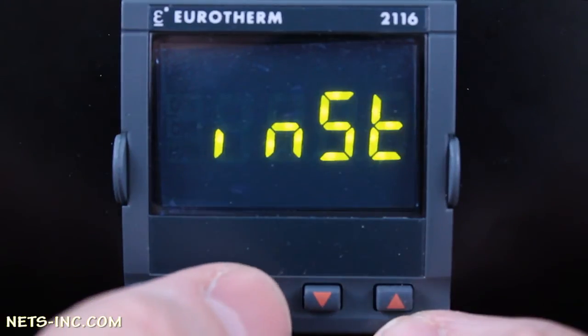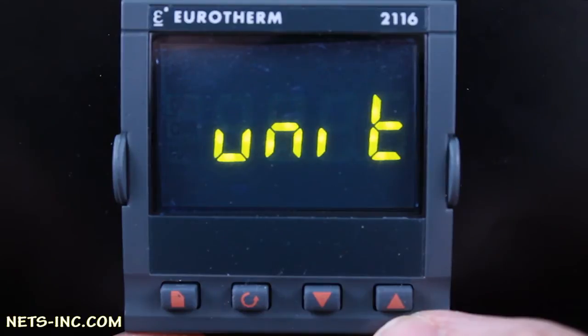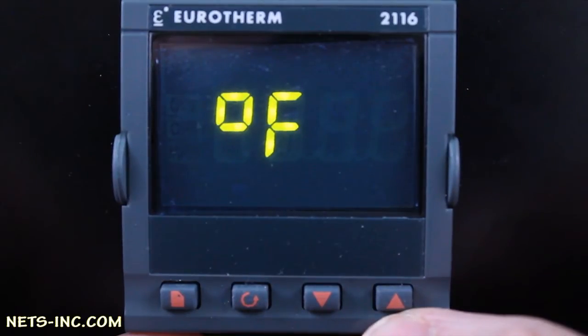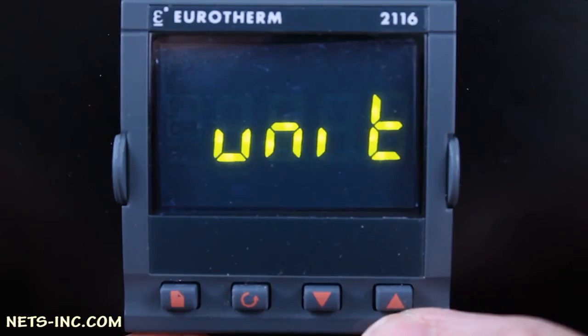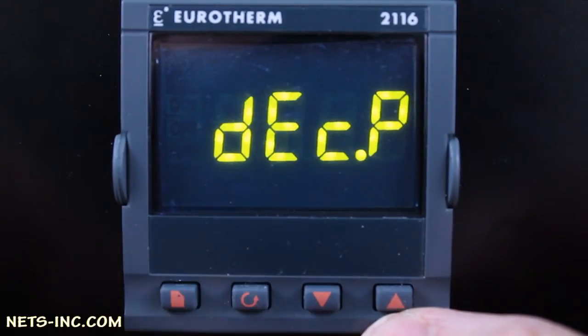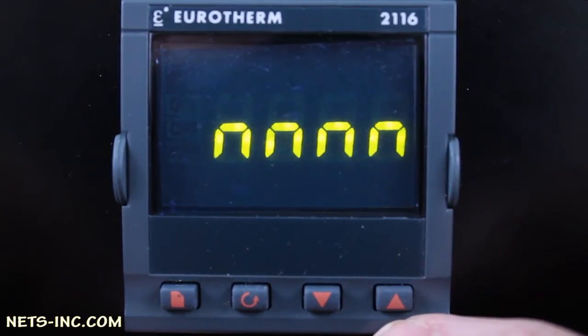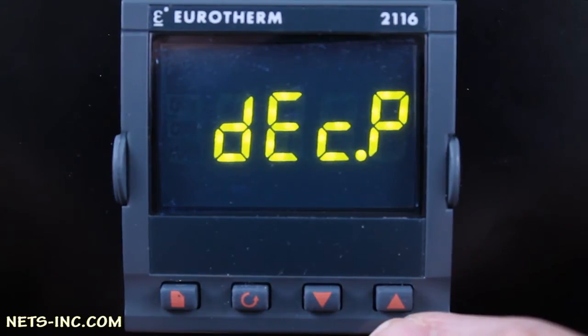With the display reading INST, press the scroll key once to drill down into the INST list and you will notice the display reads UNIT. Press the up arrow and the unit is set up in degrees Fahrenheit. To change it to anything other than degrees Fahrenheit, continue hitting the up arrow and more selections are available. Press the scroll key again and the display will read DEC.P, which is decimal point. Press the up arrow and for our application we are not going to have any decimal points. Should you want a decimal point, continue pressing the up arrow and you will notice the decimal point marches across the screen.